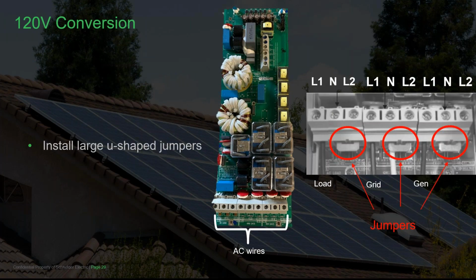Next, the large jumpers are used to short L2 to neutral on grid and generator input terminals and also the load terminal. Note the AC wiring terminal block identified in the photo. Also note the photo to the right showing the bottom fed AC wiring terminals populated with load, grid, and generator wires, along with the position of the large U-shaped jumpers.